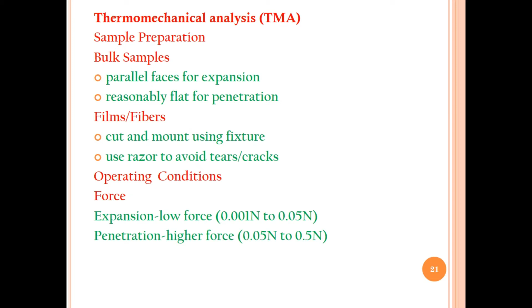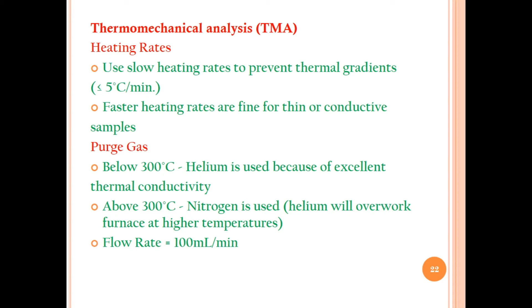Heating rates are also an important parameter to be considered in TMA. Use a low heating rate to prevent thermal gradients. It should be less than or equal to 5 degrees per minute. Faster heating rates are fine for thin or conductive samples. Purge gas: again, the importance, the nature of the purge gas. Below 300 degrees Celsius, helium is used because of its excellent thermal conductivity. It was already discussed in a former slide. Above 300 degrees Celsius, nitrogen is used. Helium will overwork the furnace at high temperature. Flow rate must be 100 ml per minute for any purge gas utilized in the TMA instrument for the analysis of any type of material for its characteristic properties.